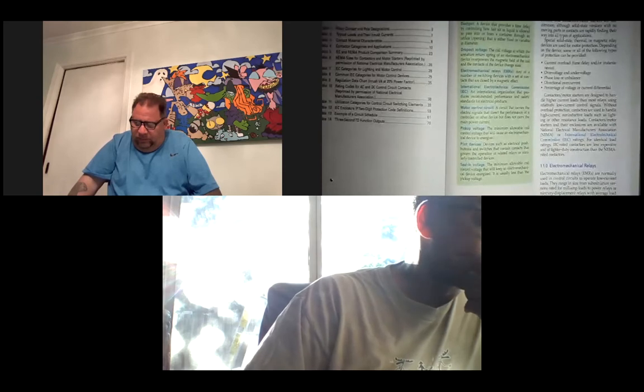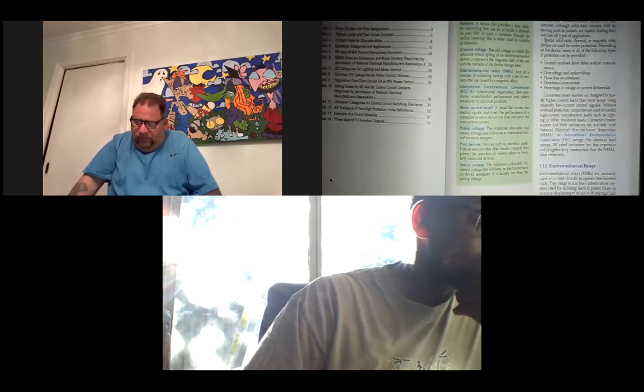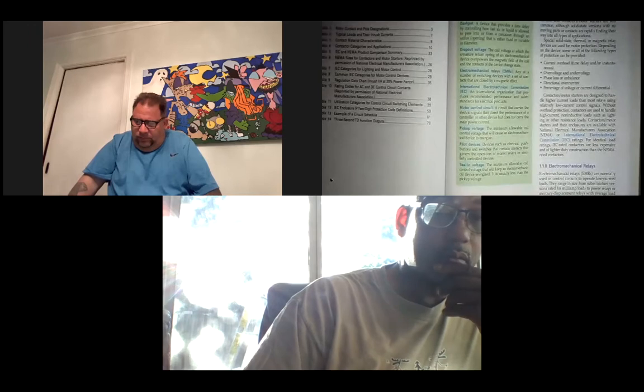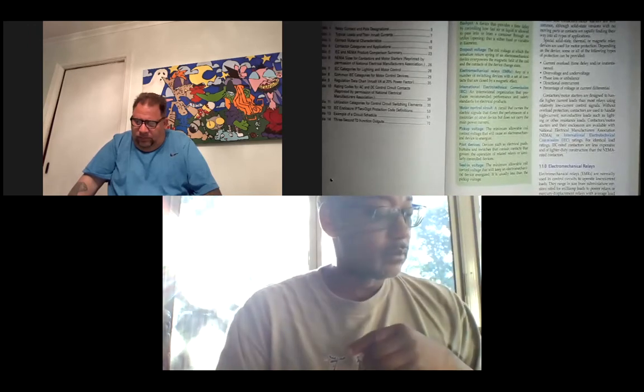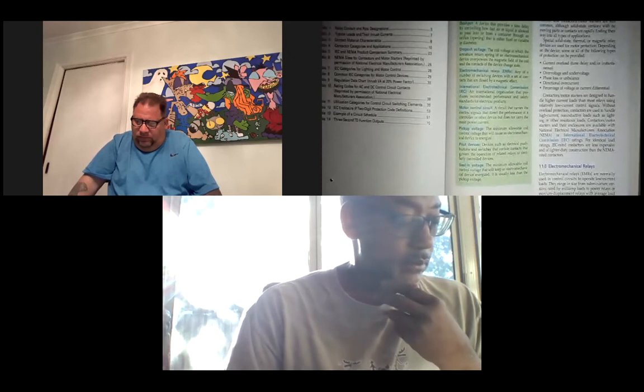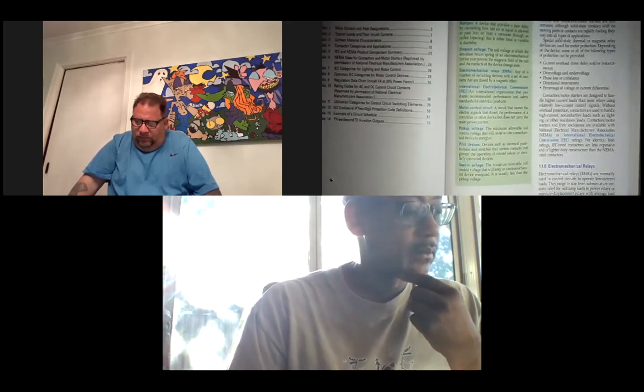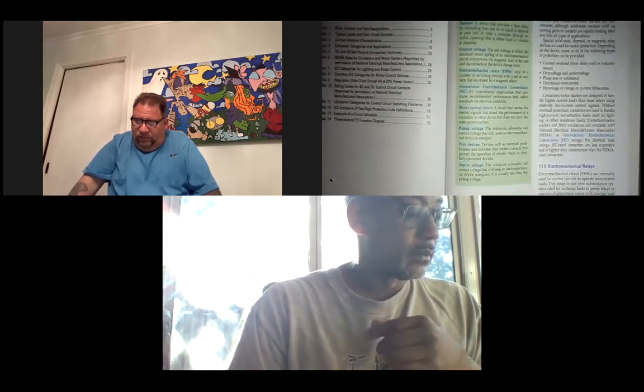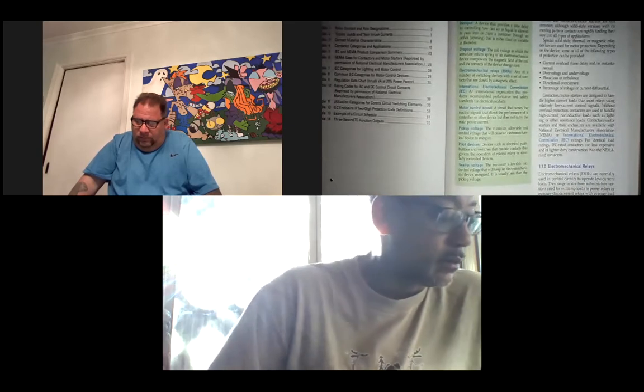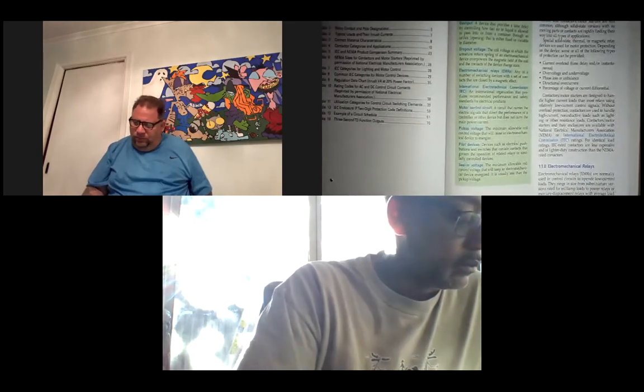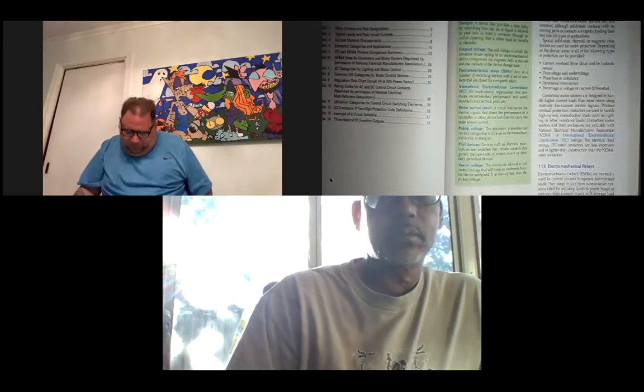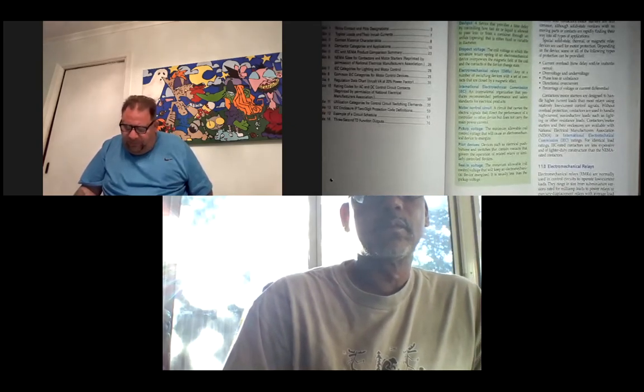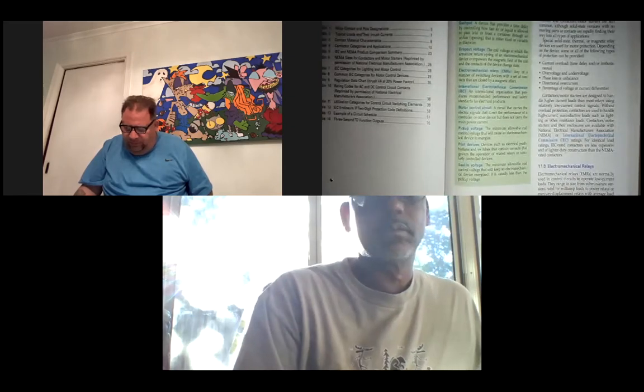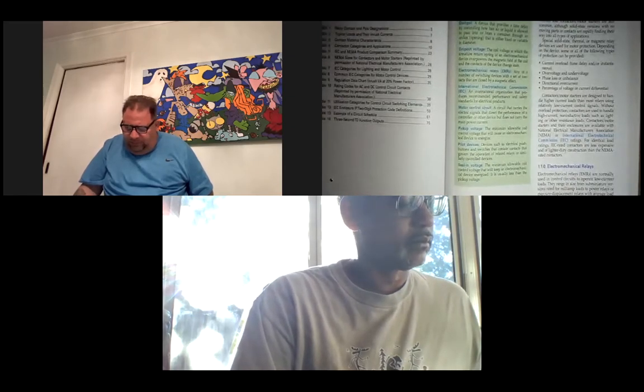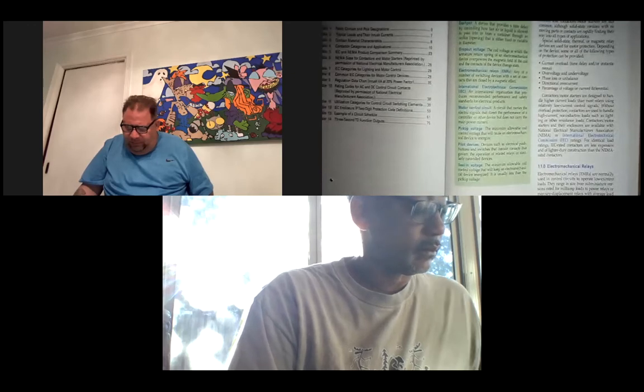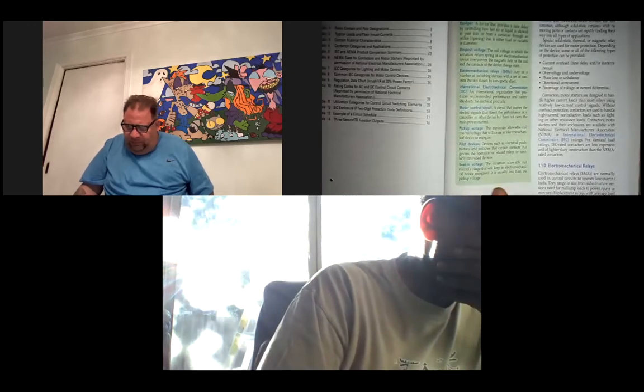Because there's a gap between the plates of the stationary core and the movable core. There's an air gap, and you have to generate enough magnetism in order to draw in that movable core. And then once it's sealed in, it's closer to the stationary core. So it takes less magnetism and thus less voltage in order to keep it sealed in.